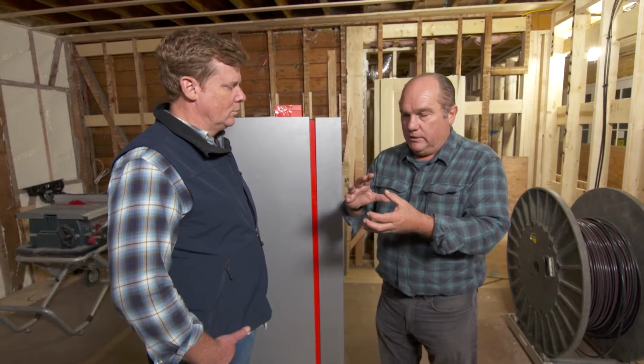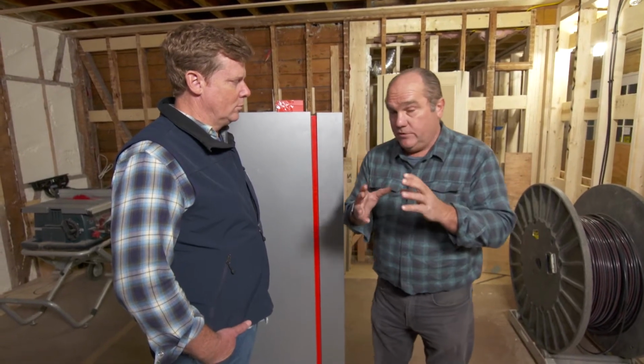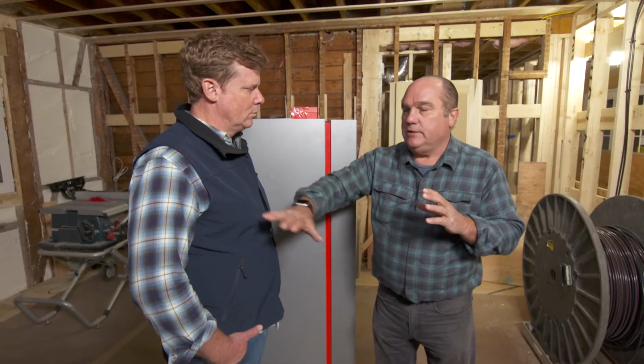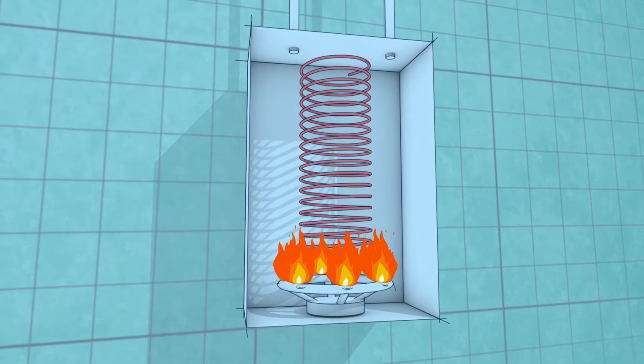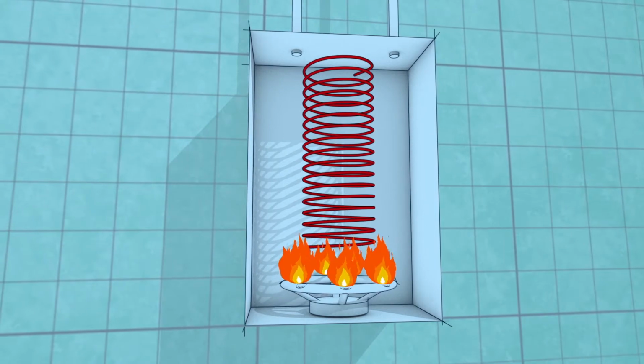And we first went into super efficient gas-fired condensing boilers. Those boilers were all relatively small and wall hung. Now those wall-hung boilers were really efficient, except the heat delivery system was looking for a gentle supply, and the boilers got so hot so quick that they fired up and got quickly hot, and then they shut off, so they cycled too much. So we really would like to have the burner stay on longer.